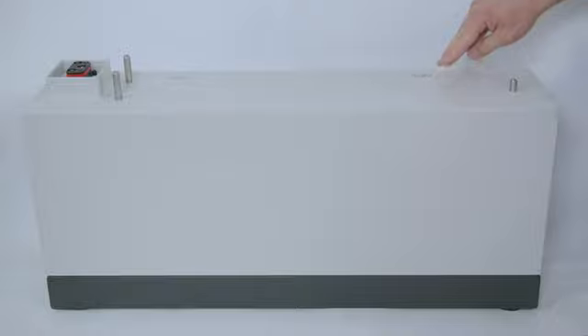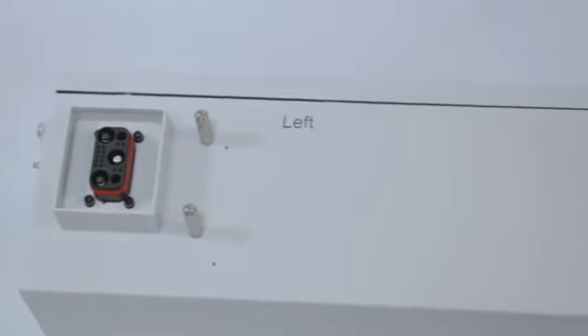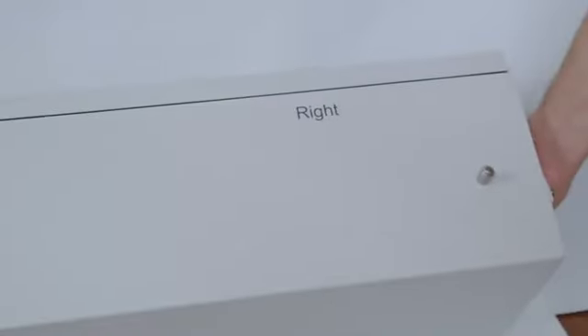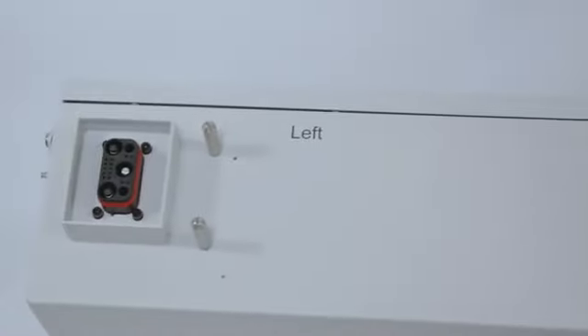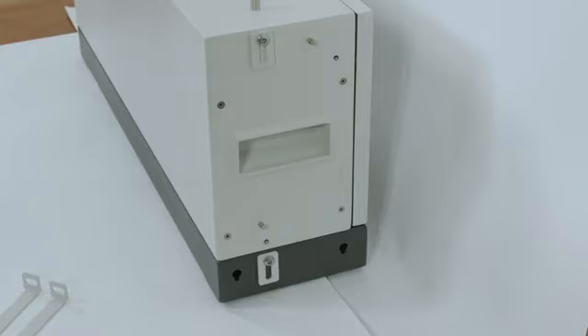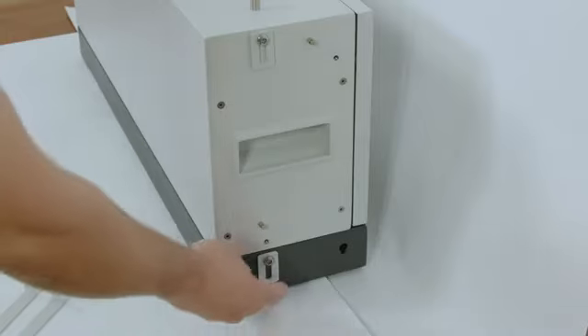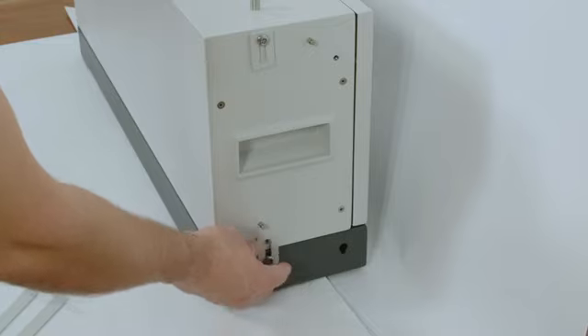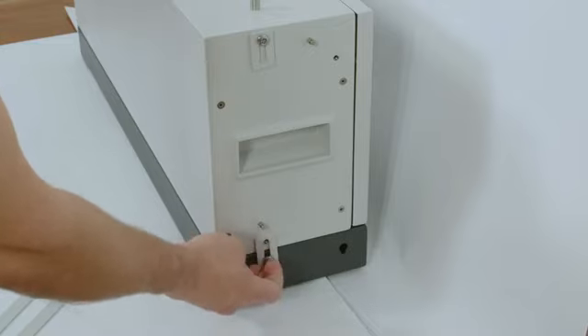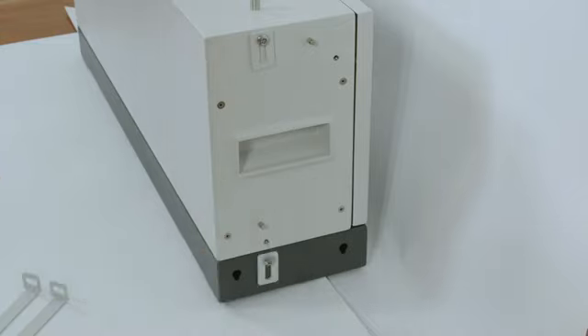Please make sure to always align the left and the right side correctly, since on the left side there is the DC plug as well as the mechanical buttons to connect the battery modules to each other. To fix the modules to each other, there are mechanical components on the side of the Reserva that can be fastened with a Torx 30 and a torque of 5 Newton meters.